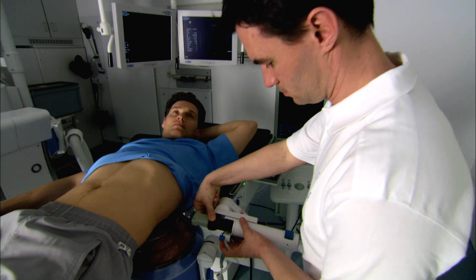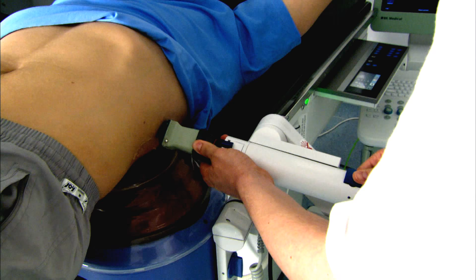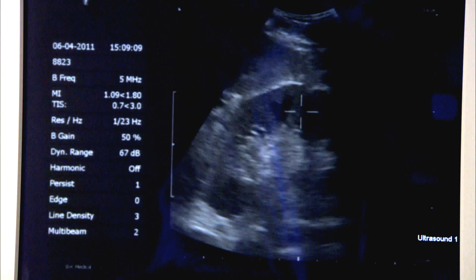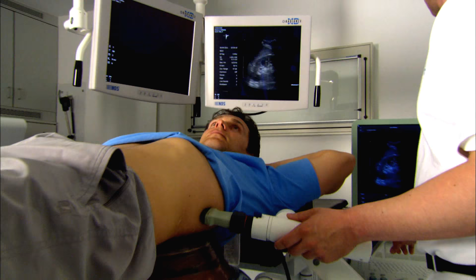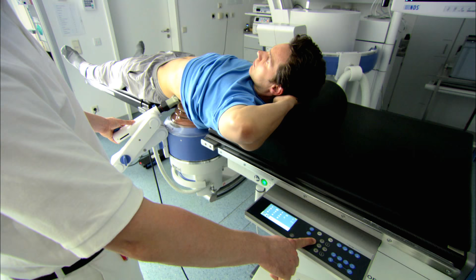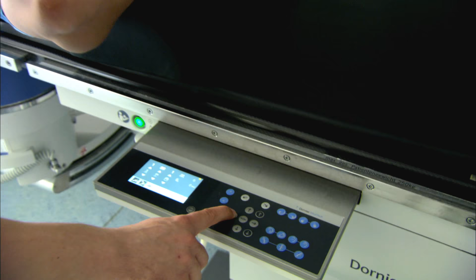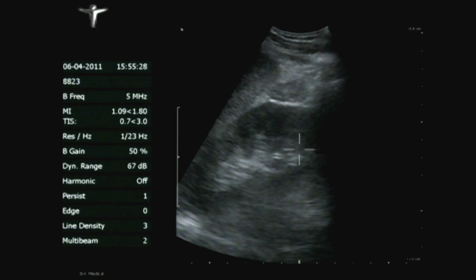In the cases where X-ray localization is not desired or appropriate, ultrasound localization is a compelling alternative with its flexibility, outstanding image quality, and freedom of interaction with the shock waves. The ability to free scan with the transducer simplifies the pre-positioning of your patient and the stone localization. The flexibility of the transducer and articulating arm provides the operator with an easy-to-use ultrasound alternative, providing an excellent acoustic window without shadowing from surrounding anatomy. Because the ultrasound transducer is in direct contact with the patient's body and the convenient ergonomics of the control panels, you have optimum ultrasound image quality and positioning capabilities.